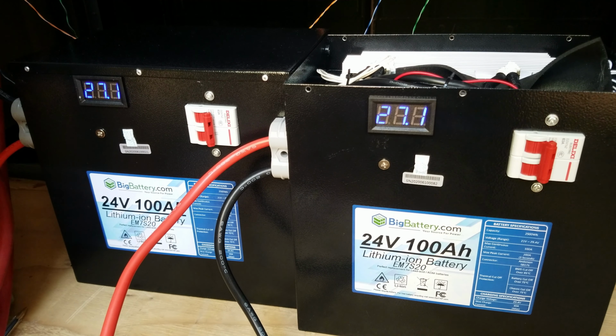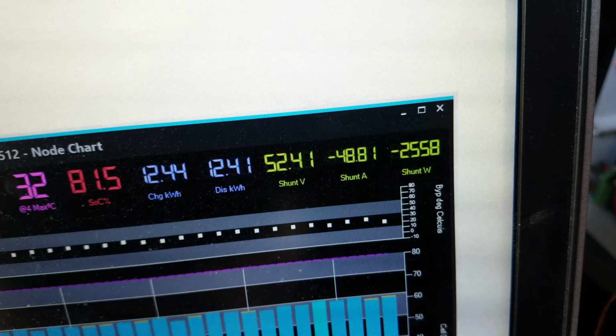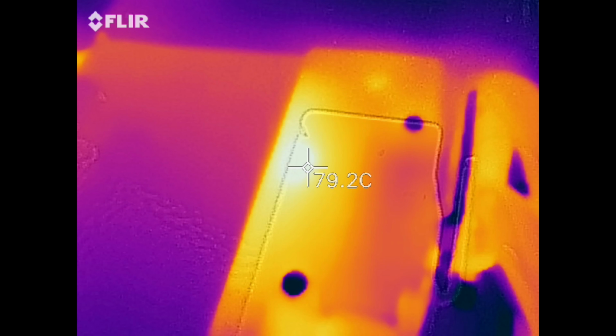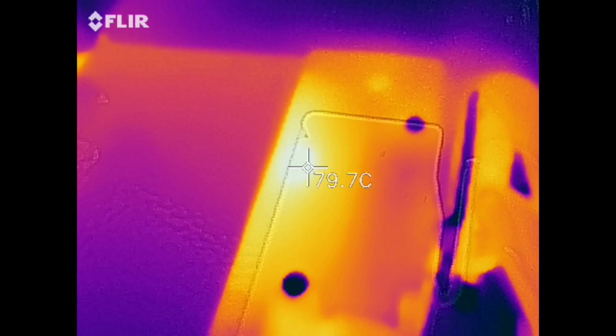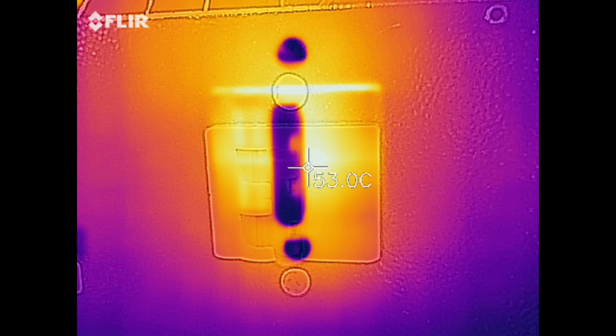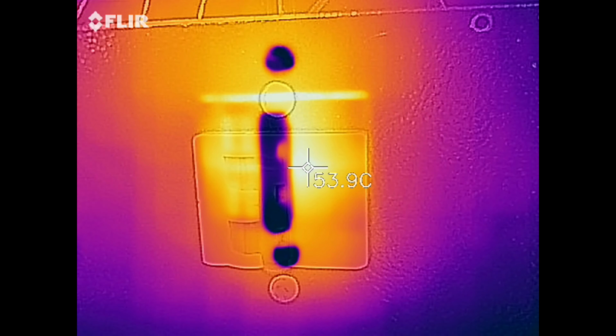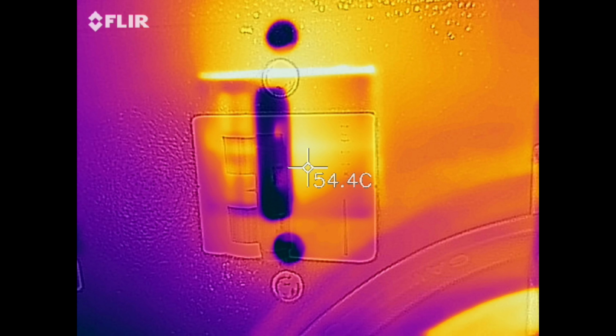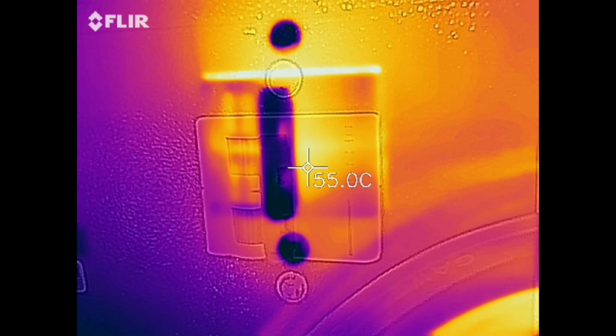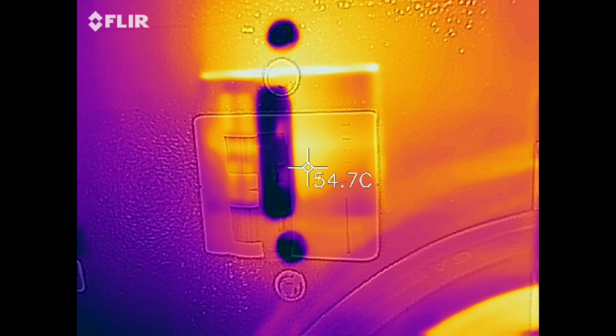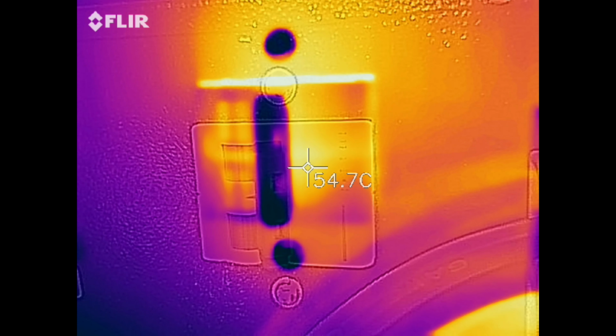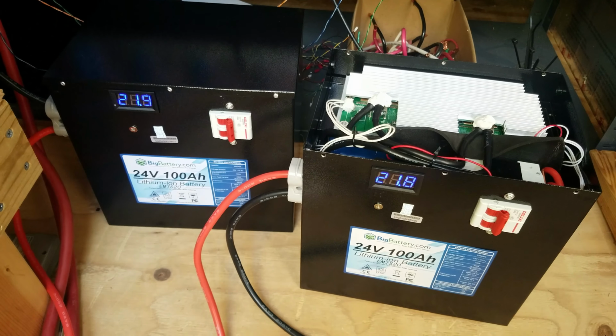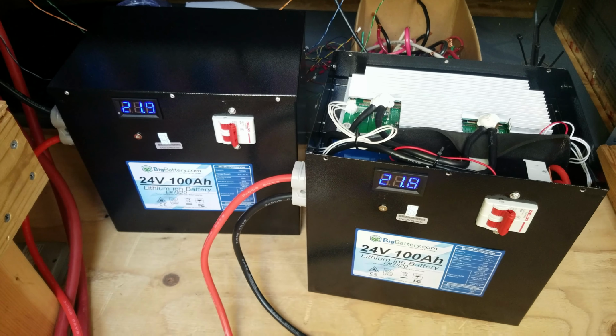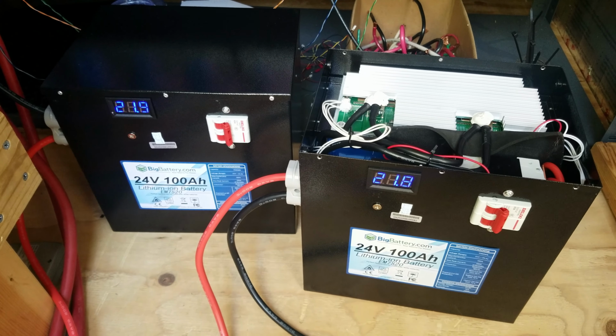Alright, so I have the air conditioner running. It's approximately a 2-ton unit. It's probably about 1.8 or 1.9 ton. You can see we're pulling 48 to 49 amps. And on the breaker, I'm seeing just under 80 Celsius. And I'm going to compare the first one. I'm seeing 53 Celsius is the hottest part, with the second one, and I'm seeing roughly the same temperature. So I don't believe it's a loose bolt unless it happens to be a loose bolt in both of these enclosures, which seems a bit unlikely. Alright guys, so we've been running for just under an hour and a half when you consider the clothes dryer test and the air conditioner.